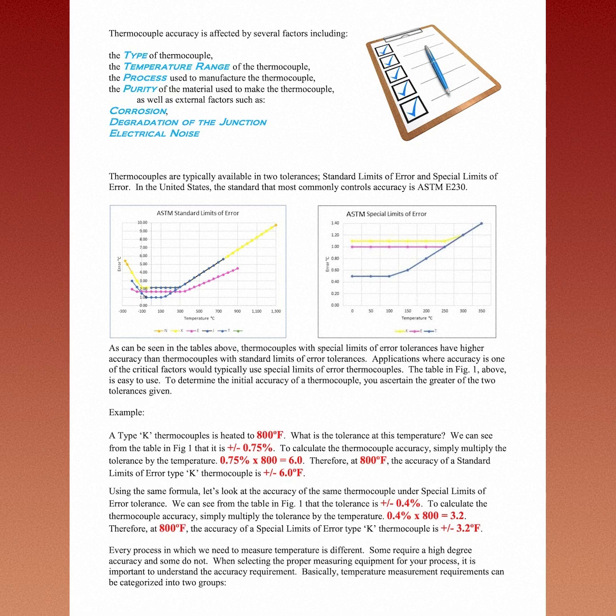Thermocouples are typically available in two tolerances, standard limits of error and special limits of error. In the United States, the standard that most commonly controls accuracy is ASTM E230. As can be seen in these tables, thermocouples with special limits of error tolerances have higher accuracy than thermocouples with standard limits of error tolerances. Applications where accuracy is one of the critical factors would typically use special limits of error thermocouples. The table in Figure 1 is easy to use.